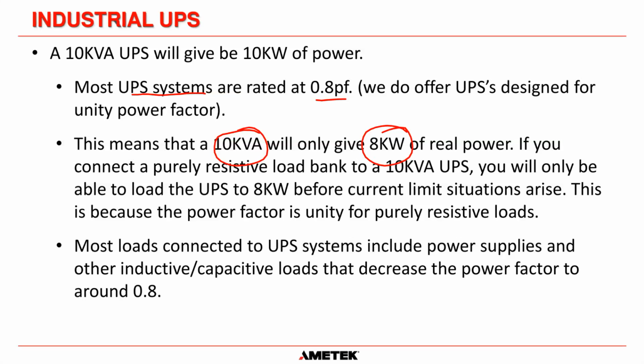So if you connected a purely resistive load bank to a 10 kVA UPS, you will only be able to get 8 kilowatts of power before the UPS says, okay, that's now going above my limitations and I'm going to do something to reduce that current. And once again, what it does is it reduces the output voltage to reduce the current. So you can only get 8 kilowatts of true power from the UPS. That's because most loads historically connected to a UPS include power supplies and other things that have inductance and capacitance, and that decreases the power factor to around about 0.8. So UPS manufacturers have just stuck with that value, and that is what we offer. But once again, we do sell UPSs that have unity power factor if you need them.